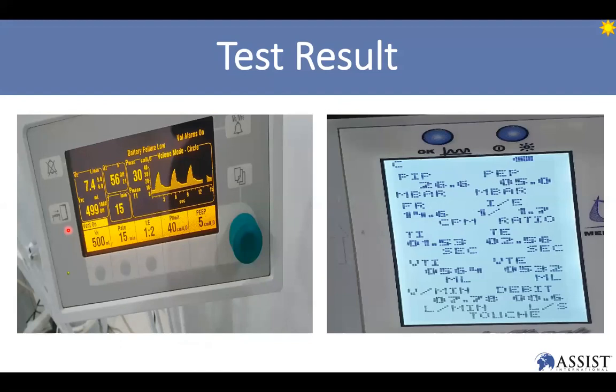here are some pictures from the vent testing that you will do. Once you've started the test, you'll set up the tidal volume, the breath rates, the IE ratios, the PEEP values, and your test device should give you something of these sorts. You will see the IE ratio here is 1 to 1.7. The ratio that was set is 1:2. And so this would be considered pass. Also, the breath rate is being recorded at 14.6. We set it at 15, and so this would be considered passing.